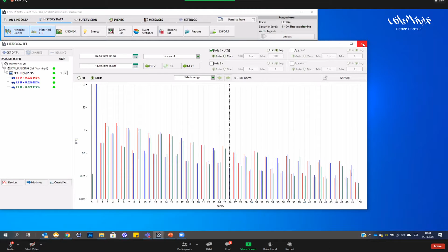One interesting thing is also the power quality. As I said, power quality is measured by the meter and then evaluated statistically. Here I can see the statistical results for all my meters, calculated each week automatically. For example, for my building, the power quality is not passing because of bad quality coming into our building; the total harmonic distortion and the harmonics are not following the limits. So I directly see the red cross showing that power quality didn't pass for each week of this year.